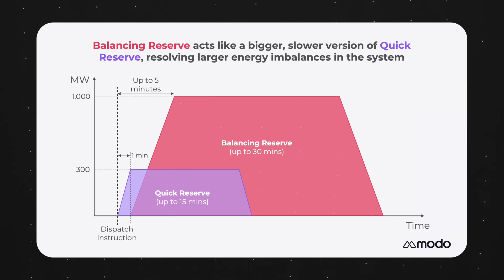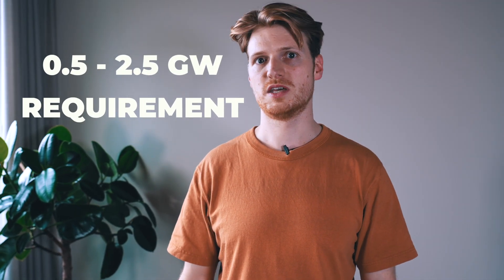Again, the idea is to solve energy imbalances in the system. The ISO is hoping to procure between 0.5 and 2.5 gigawatts of the service, and the auctions are run each morning ahead of the day-ahead auctions for the wholesale market. But will it be suitable for batteries? Well, the technical requirements do fit in with what batteries can provide, but the insistence that providers will be able to provide mandatory frequency response does throw a spanner in the works.